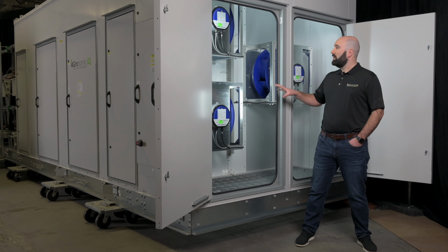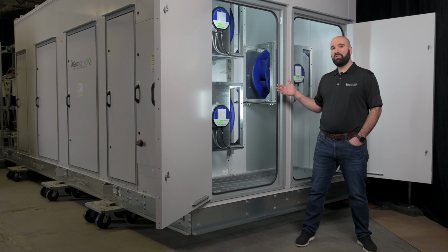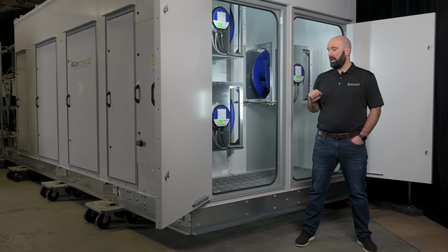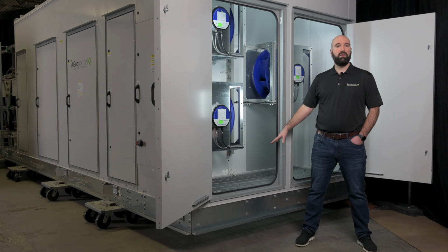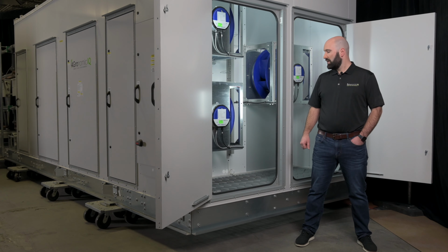In this compartment as well, again, you see the 3 redundant fans. We talked already about the backdraft damper on the front of those fans. There's an air-proving switch, and then just a personnel safety grate, ensuring that nobody has the opportunity to fall through the machine into the building in the event of servicing. That's the end of the airflow section. Let's go take a look at dry coolers.